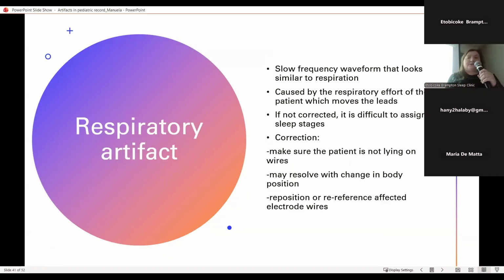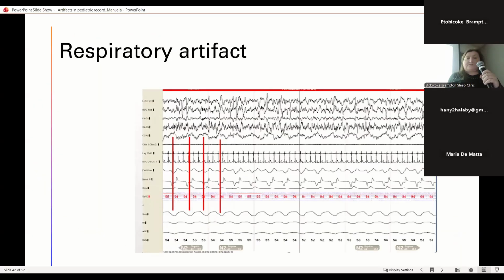Respiratory artifact: a slow-frequency waveform that looks similar to respiration, caused by the respiratory effort of the patient moving the leads. If not corrected, it is difficult to assign sleep stages. As a correction, make sure the patient is not lying on wires. It may resolve with a change in body position, repositioning, or re-referencing the affected electrode wires. So this is the respiratory artifact. It's aligned with the respiration, if you notice.